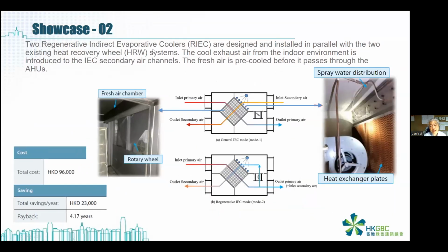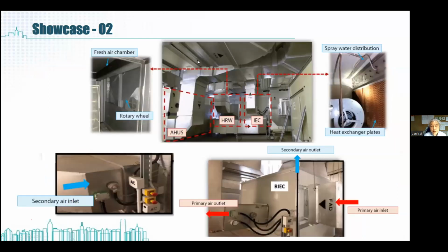This is the design for a wet market in a housing or residential center. They are using indirect evaporative cooling, so you can see here the thermal wheel together with the humidifiers, which use evaporation to further cool down the return air before it is exhausted from the building, to cool the primary air, so that this is more effective. They use evaporative cooling. This is their setup. One of the disadvantages is that they need quite large mechanical spaces when you are doing this kind of thing. This is the disadvantage of this kind of technology.